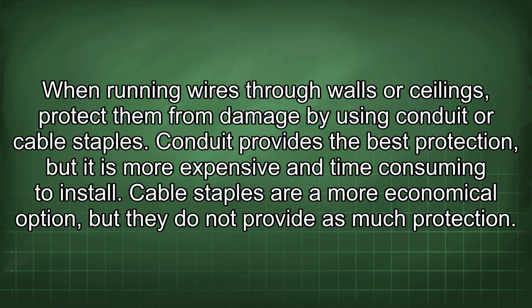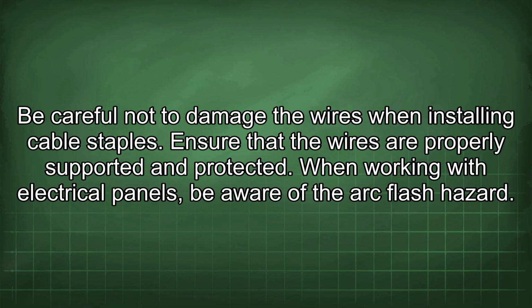When running wires through walls or ceilings, protect them from damage by using conduit or cable staples. Conduit provides the best protection, but it is more expensive and time-consuming to install. Cable staples are a more economical option, but they do not provide as much protection. Be careful not to damage the wires when installing cable staples. Ensure that the wires are properly supported and protected.